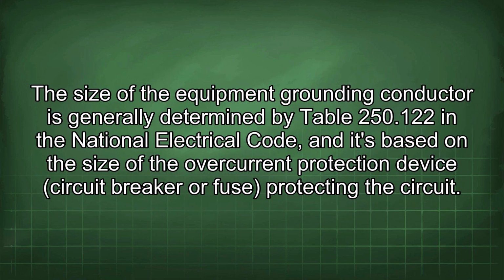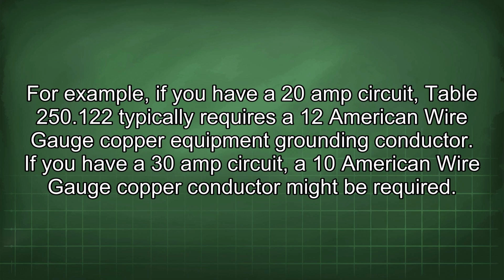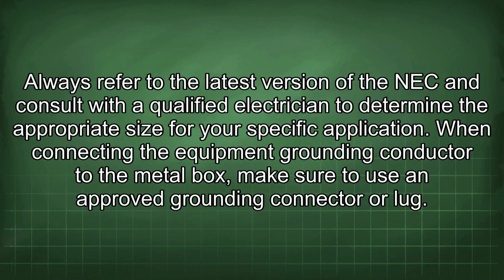The size of the equipment grounding conductor is generally determined by Table 250.122 in the National Electrical Code, and is based on the size of the overcurrent protection device, circuit breaker or fuse, protecting the circuit. For example, if you have a 20 amp circuit, Table 250.122 typically requires a 12 American wire gauge copper equipment grounding conductor. If you have a 30 amp circuit, a 10 American wire gauge copper conductor might be required.